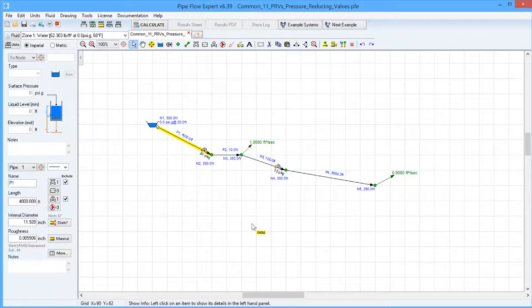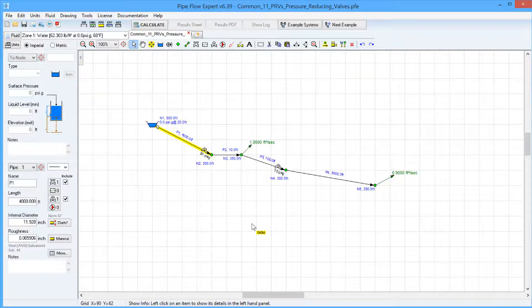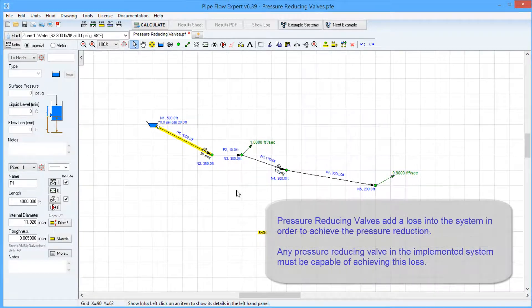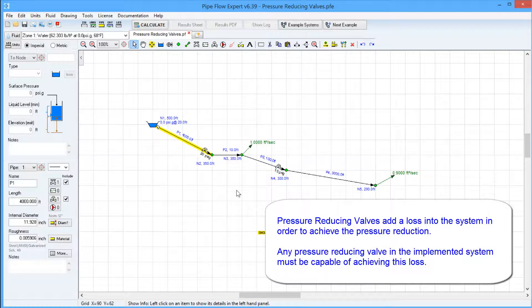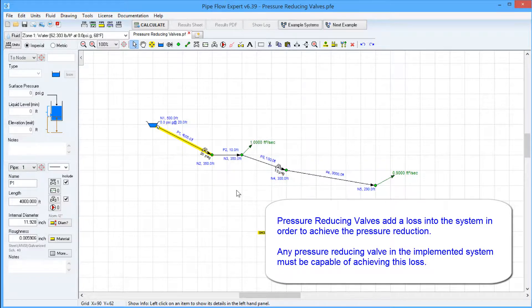All three of these options will bring up the set control data, where we select the pressure reducing valve radio button and define the pressure that we want. A pressure reducing valve cannot add pressure — if the pressure reducing valve pressure setting is higher than the maximum pressure that would occur at the following node, the system will not be solved. The pressure reducing valve has to add loss into the system, and therefore any selected valve for the real-world system needs to be capable of adding this loss.